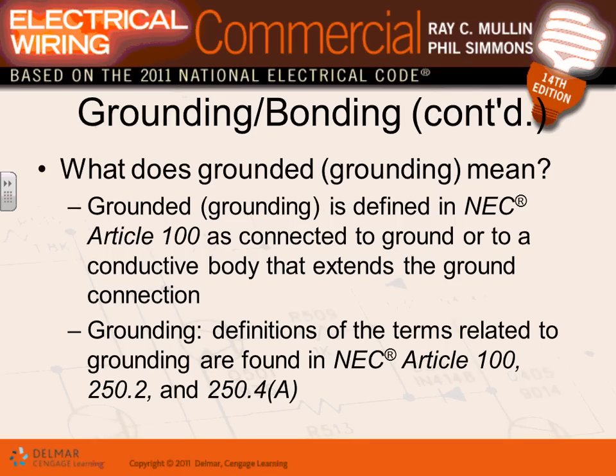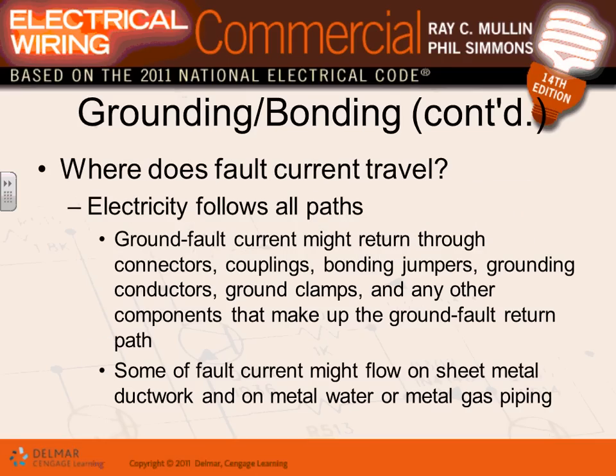Does grounding mean connecting a conductor to the ground or extending the ground? There's a lot of definitions about grounding, guys. When you say grounding a system, you're intentionally connecting one wire of that system to the ground. So the fault current travels in all directions. So that's why when we have your conduits, Adam, if you have a ground fault right now in this conduit, the current will go through the equipment grounding conductor, if any, as well as through the conduit.